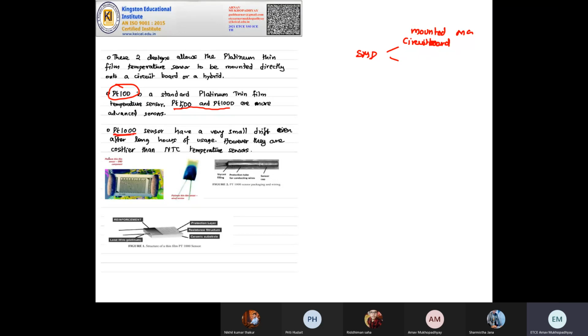Why is PT1000 more advanced and popular recently? First, it was not produced during the days of PT100, but now, by the advancement of technology, you will be able to have very small thermal drift, meaning the sensed temperature value wouldn't change with time.